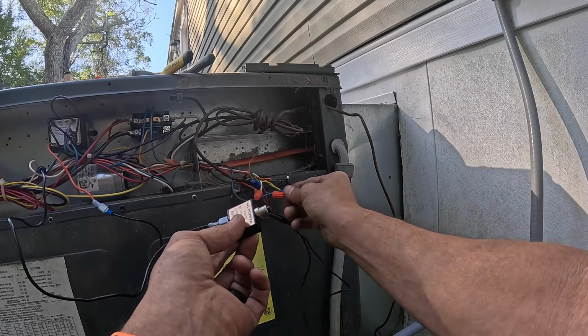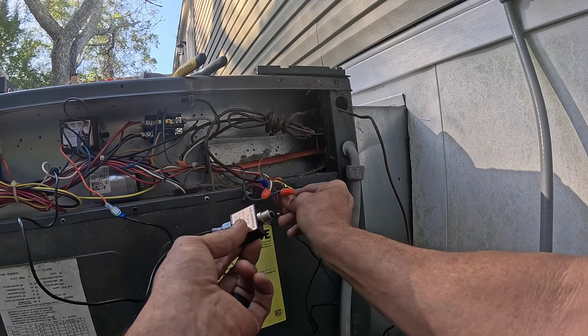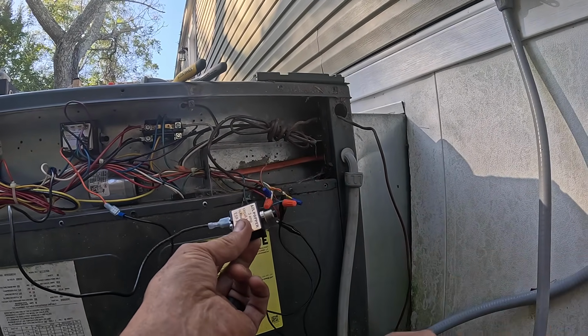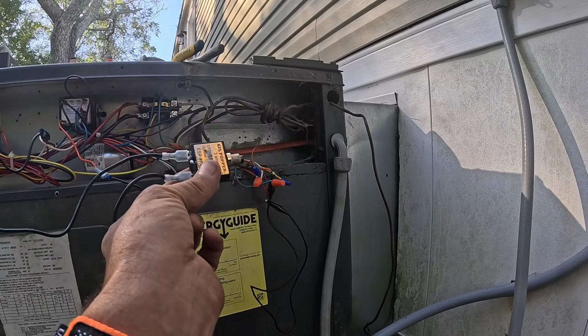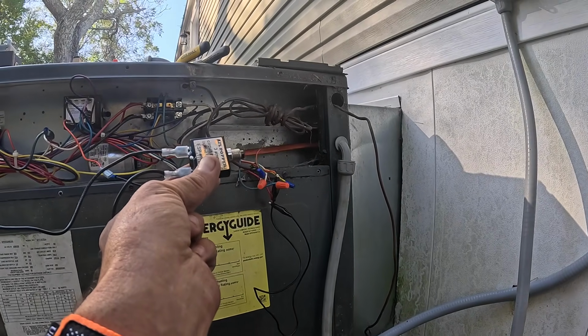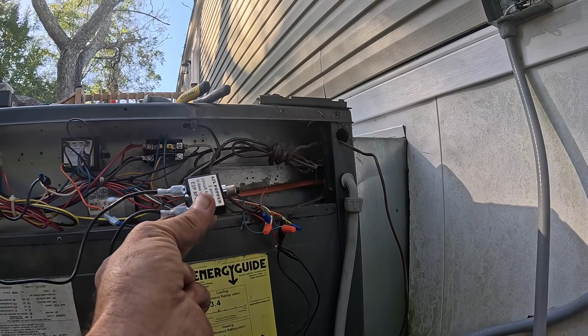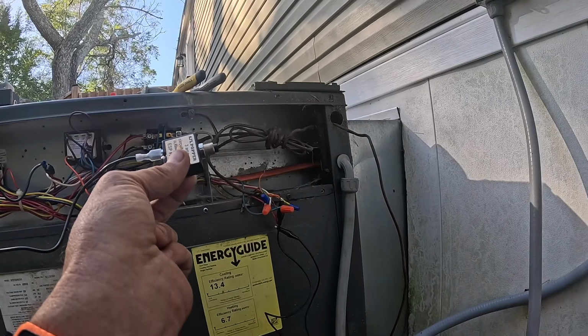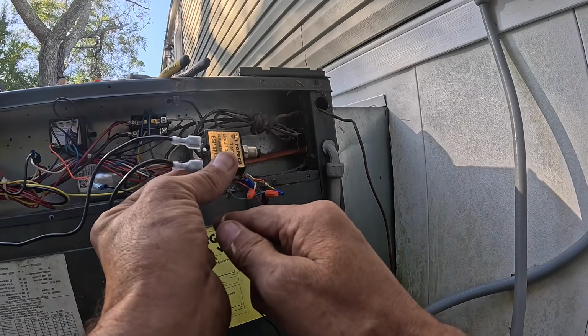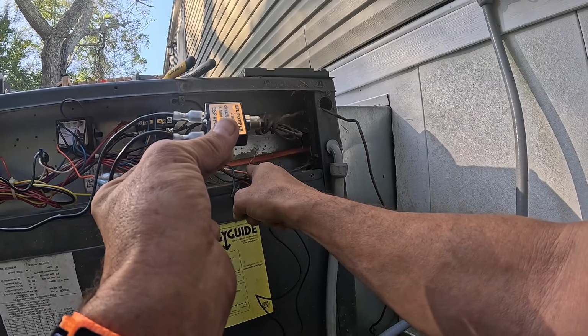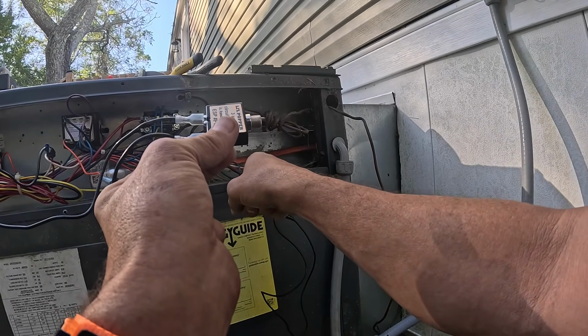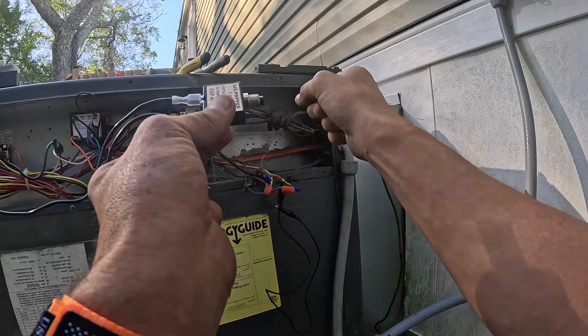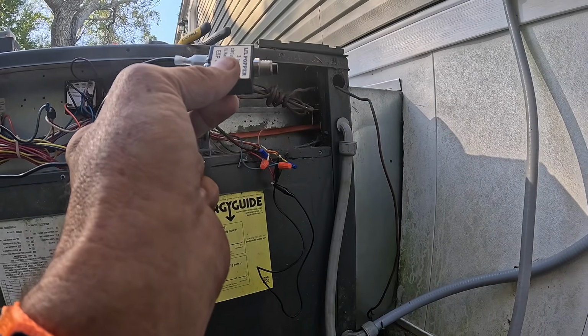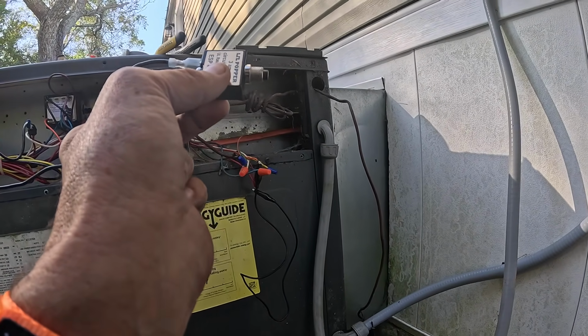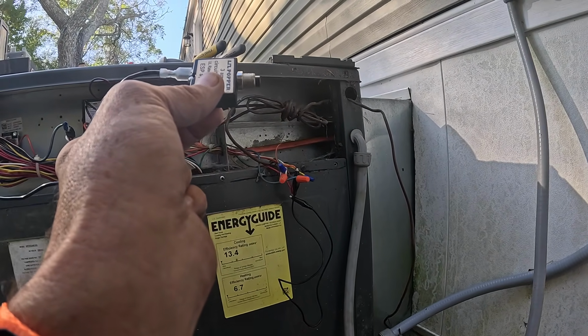Y'all hear that? All right, that's what it's supposed to sound like. There's nothing wrong in this system. This is not popping my little popper, which tells me my low voltage short is somewhere between here and my thermostat, which is not good.